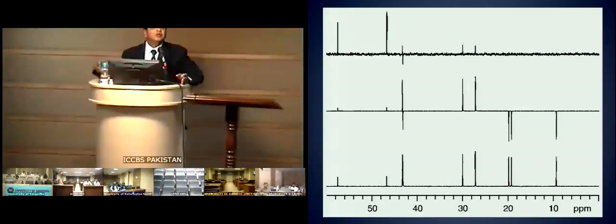People were developing cryoprobes, probes in which sensitivity increases with gaseous helium. When gaseous helium is introduced into the electronics of the probe, they cool down and you have less resistance, more conductance, the noise is reduced, sensitivity increased.